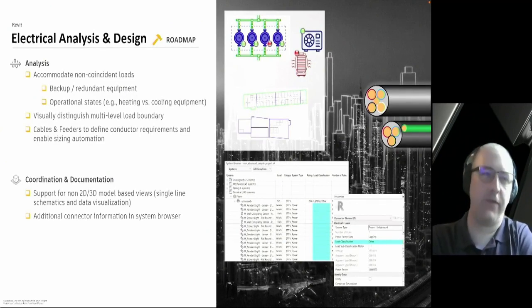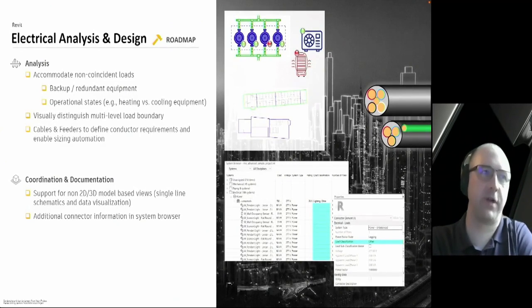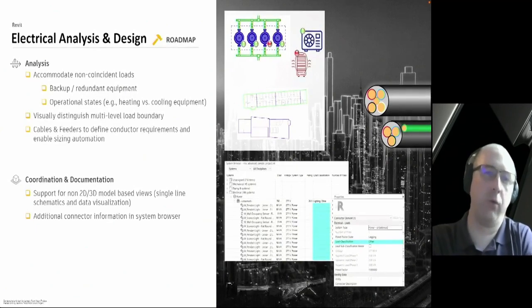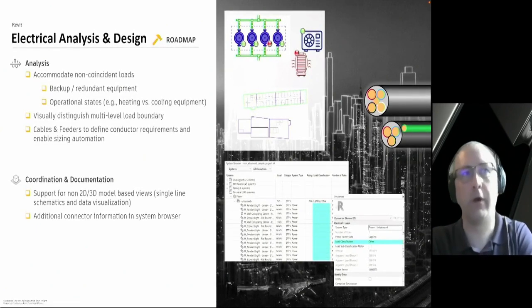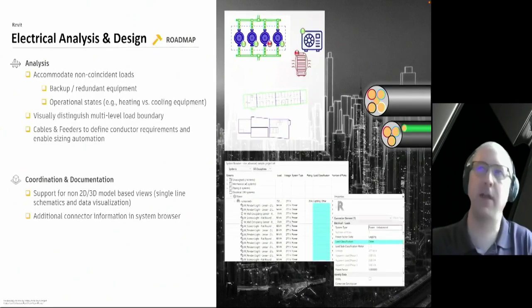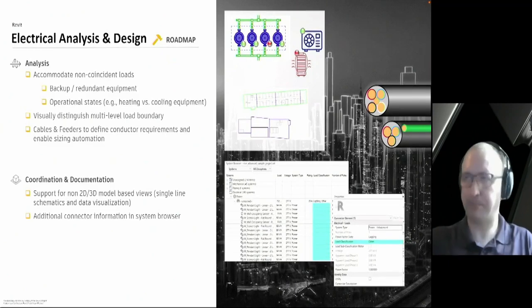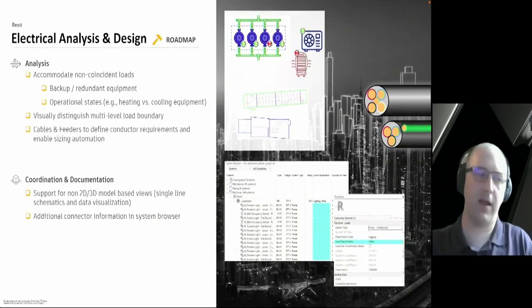Similarly, you could have equipment with different operational states—equipment that only runs during heating seasons, or only during cooling seasons, so they won't run at the same time. That's another scenario where the electrical system could be optimized for non-coincident loads. That's the next step in that analytical workflow.